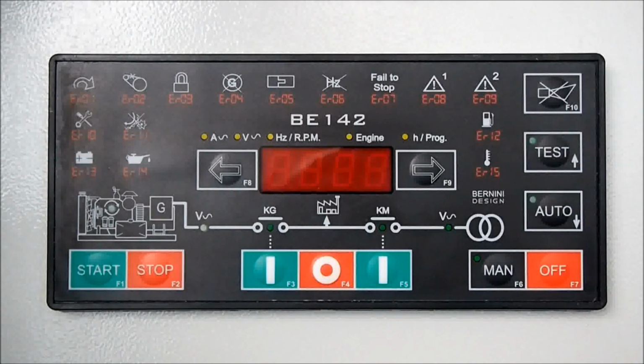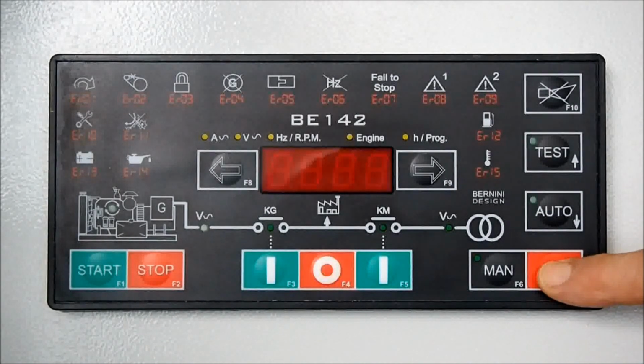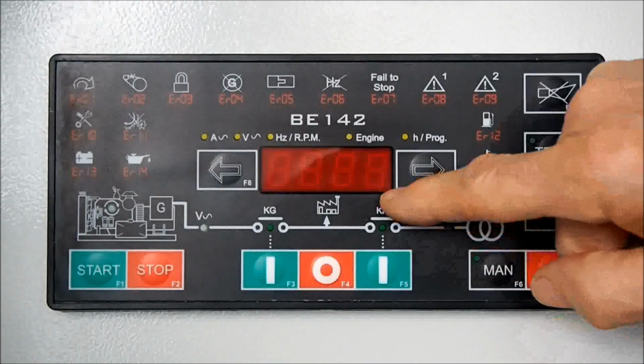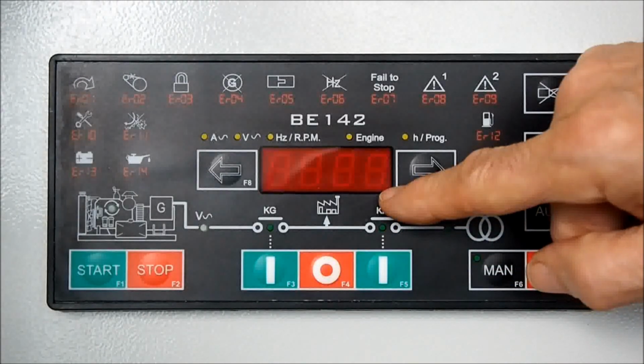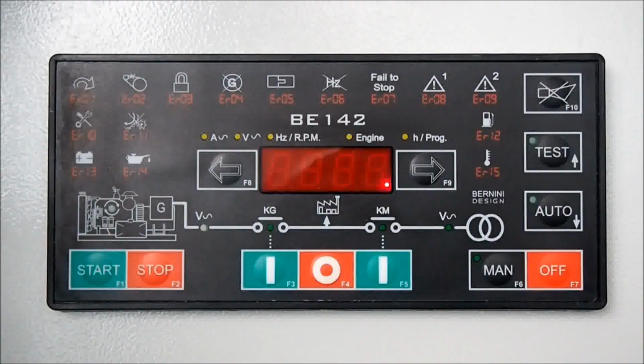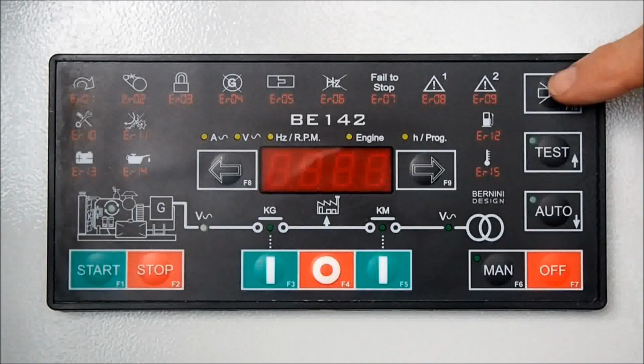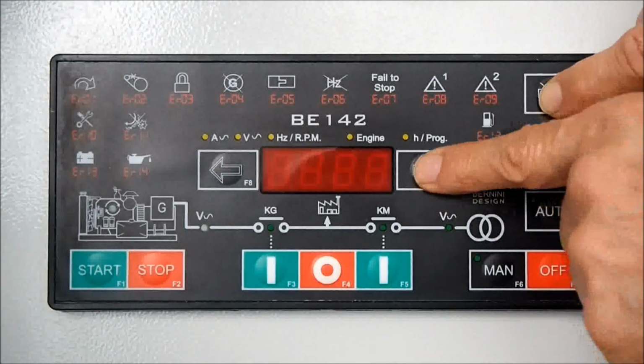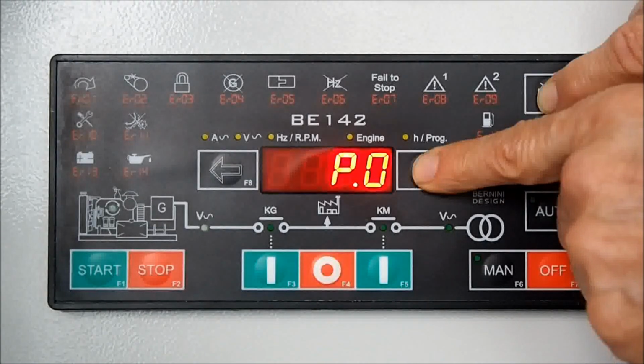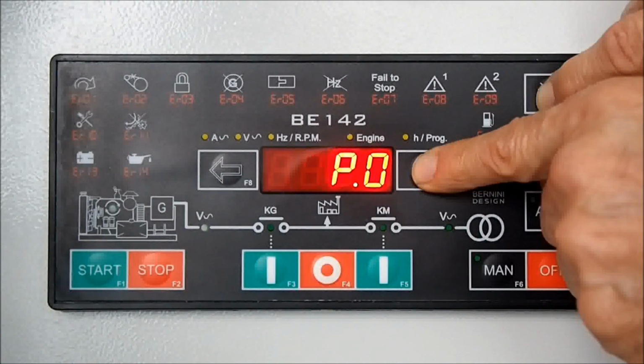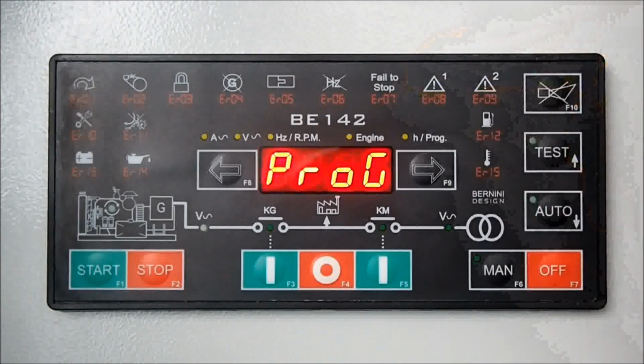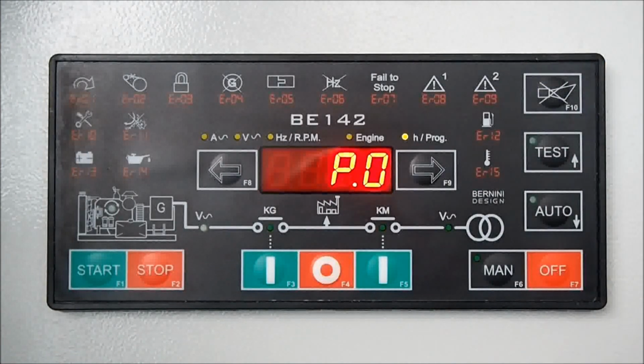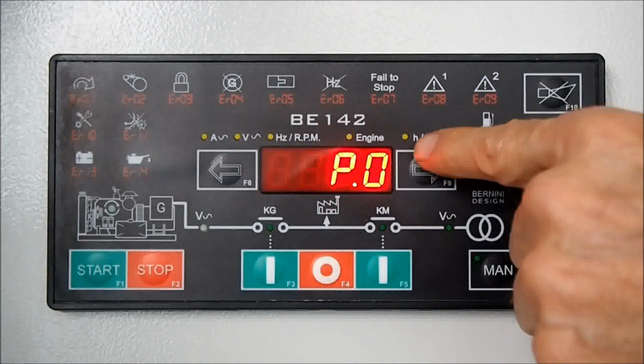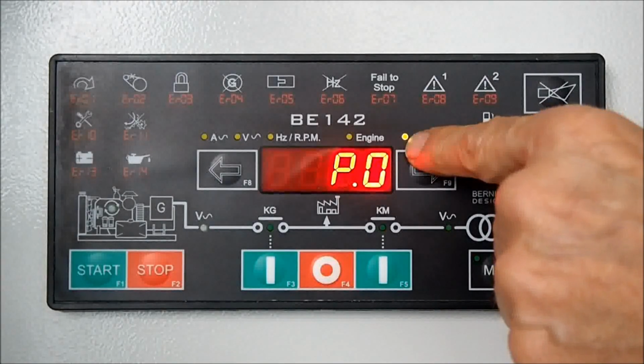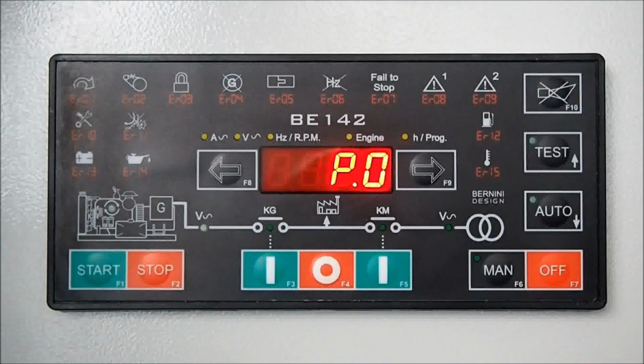To enter program mode, first of all, make sure you are in off mode. The red LED must blink. Simultaneously push F10 and F9 for a few seconds until the message prog appears on the display. You are now in program mode. You see the yellow LED is now blinking.